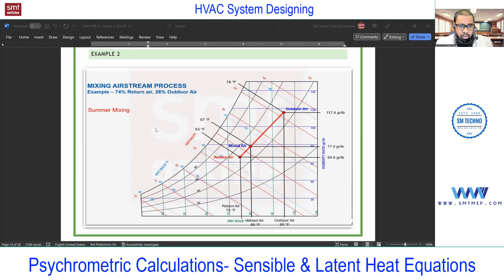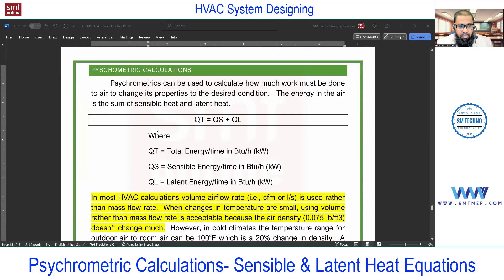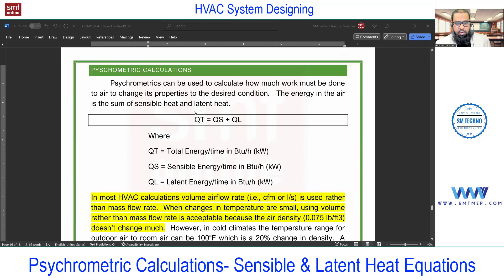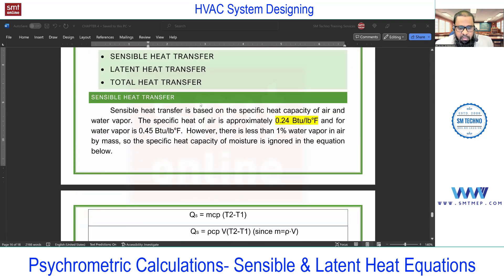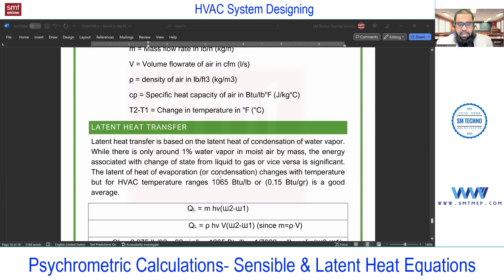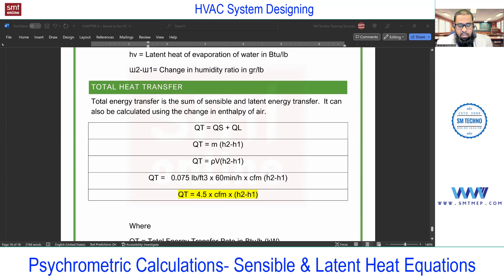We have three very important equations to discuss that we'll use at the time of load calculation. In segmented calculations you'll find three equations: one is for sensible heat, one is for latent heat, and one is a combination — the total. The first equation is Qs = 1.08 × CFM × ΔT, the second is 0.68 × CFM × Δw, and the third is Qt = 4.5 × flow rate × Δh.